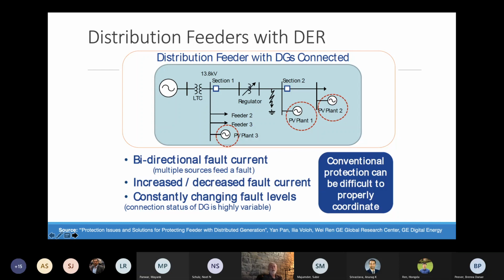If we have a distribution feeder similar to the one represented here, which I borrowed from a presentation from colleagues in GE Energy, this distribution feeder has distributed generators in the form of power plants, PV plants 1, 2, and 3, labeled and presented here, and they can start contributing to the loads, which are shown as arrows. Feeder 2 and feeder 3 can be viewed as loads from the 13.8 kilovolt bus bar, but they can be scattered across these lines. And instead of unidirectional fault current coming from the substation, where the generator representing the rest of the transmission network, an LTC load tap changing transformer representing the substation are situated on. So current is coming from the substation, but it could be coming from PV.